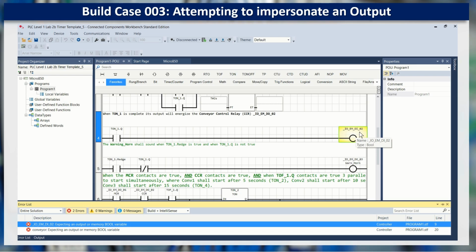It'd be like trying to short it out, which is not what you want to do. That's a bad thing. Now, some PLCs have had the ability to put a 1 in what they used to call the image table, and you could trick it for a scan, and then other PLCs you could actually write an output turning on an input so that the input would be true in the logic. But those are the exception, not the rule, and this is considered to be very bad form. And it's a simple fix.